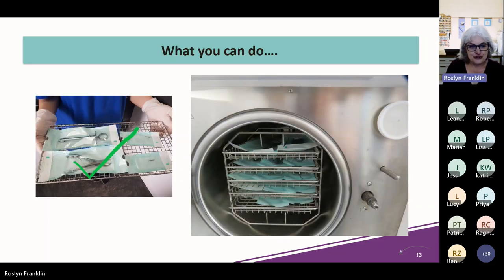So here's how it should have looked—and that's a lot less instruments, isn't it? This is why if you have a practice with a lot of instruments running one autoclave, you might need to consider the instruments you're using and perhaps add another autoclave, purely to put the instruments through properly so they're sterilized properly.